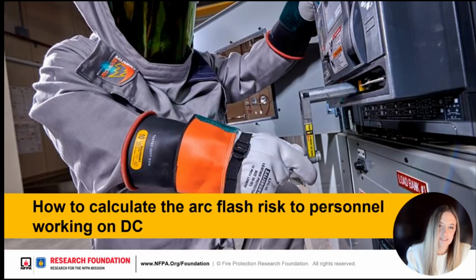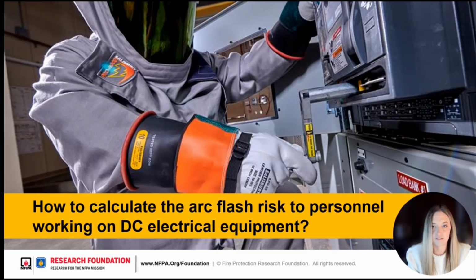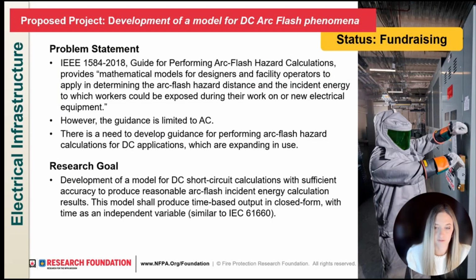As the rise in DC electrical equipment increases, worker safety must also be kept top of mind, as arc flash risk is an increasingly important issue that needs to be better understood from the DC equipment side, and how do we calculate that risk to personnel working on this equipment.